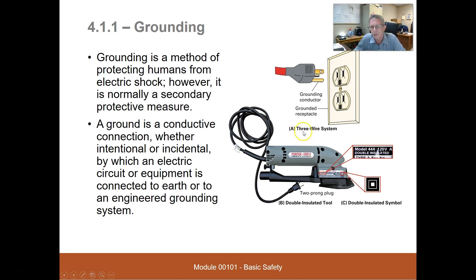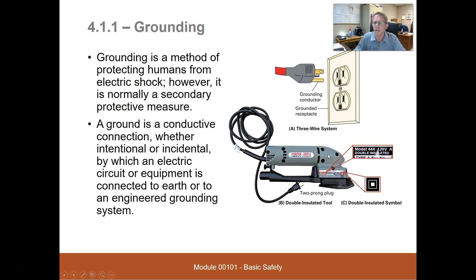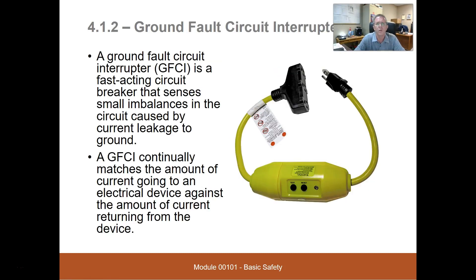Another option to eliminate the need for that third prong is to buy double-insulated tools. The symbol is a square inside a square, or it will say 'double insulated.' That means all the electrical parts inside have been insulated once, and then on the outside all the parts you touch have a second layer of outer insulation. Double-insulated tools do not require a grounding prong.